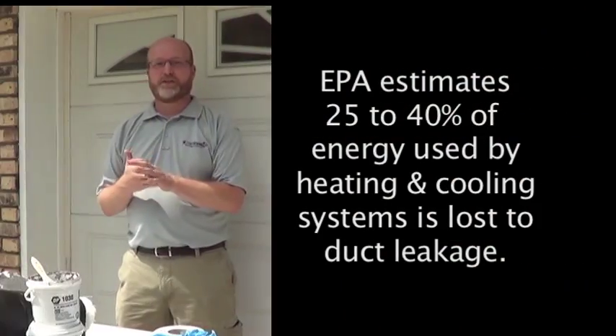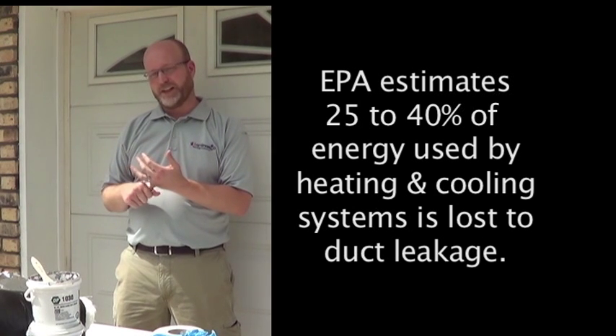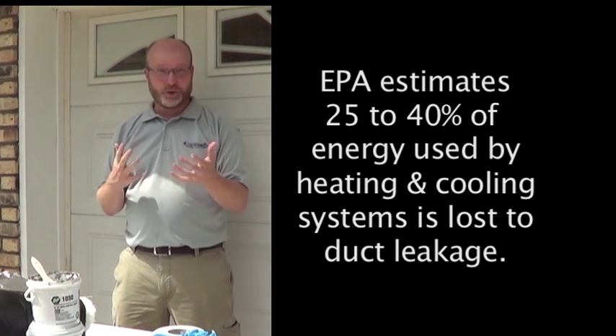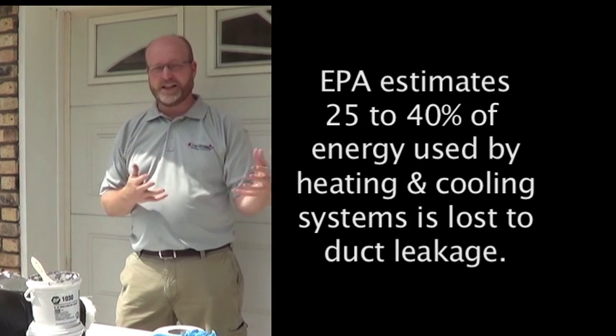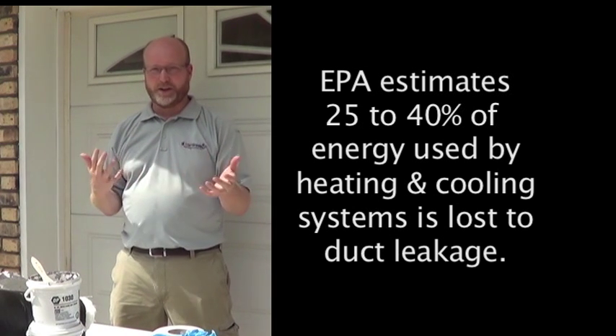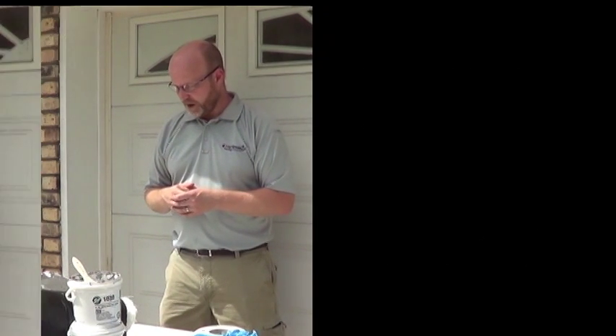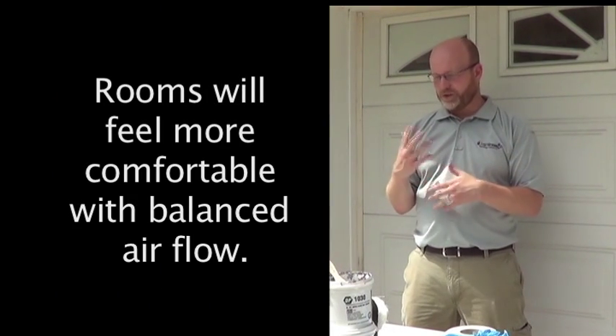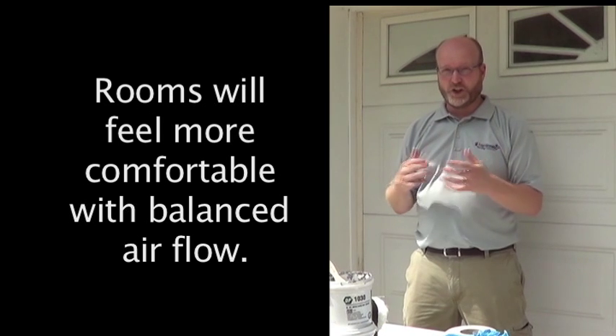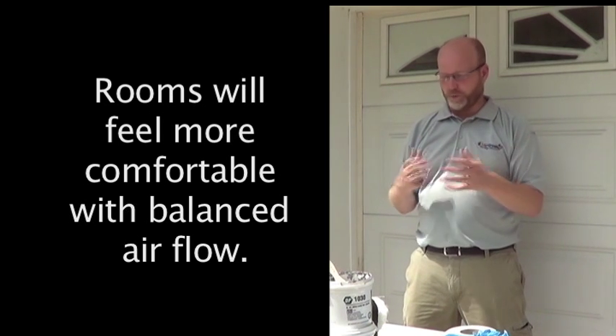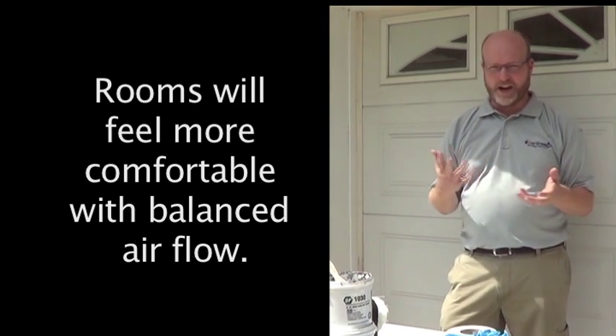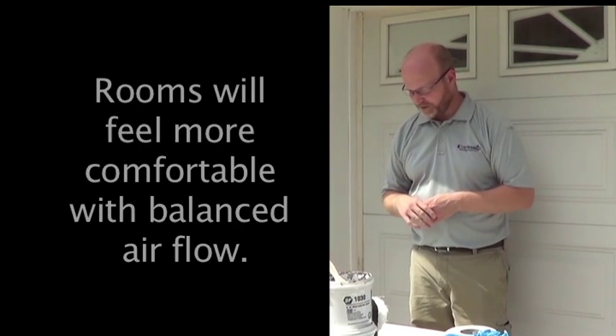Well, the EPA tells us that 25 to 40% of the energy used by our heating and cooling systems can be lost to duct leakage. So certainly there's an energy penalty there that we're concerned about. But there are other reasons. If you want a comfortable home and you use duct systems to provide the heating and cooling, we want to make sure that they're balanced well and that you're getting the air to the areas that you want.